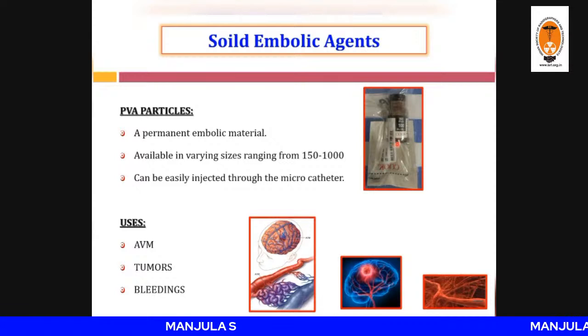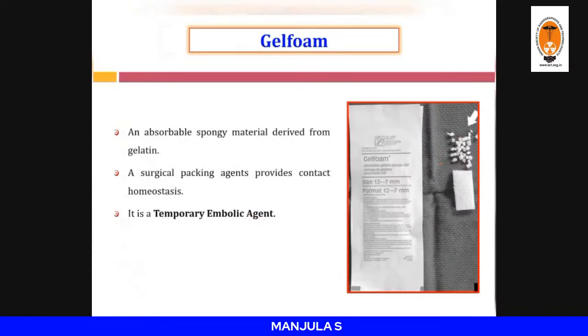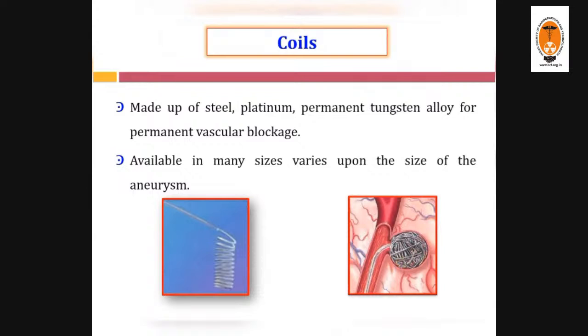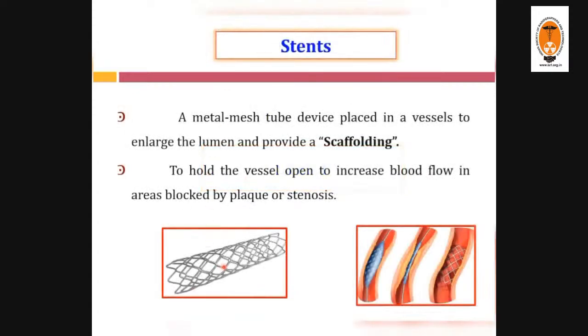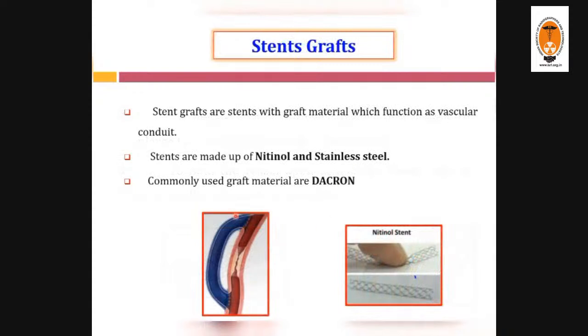Next is coils, made up of steel, platinum, or tungsten alloy for permanent vascular blockage. It is available in many sizes, varying upon the size of the aneurysm. Turning on to the next topic, stent. Stents are metal mesh tube devices placed in a vessel, enclosed in the lumen to provide scaffolding to hold the vessels open, to increase the blood flow in areas blocked by plaques and stenosis. Stent graft: a stent with graft material which functions as a vascular conduit. It is made up of nitinol and stainless steel. The commonly used graft material is Dacron.